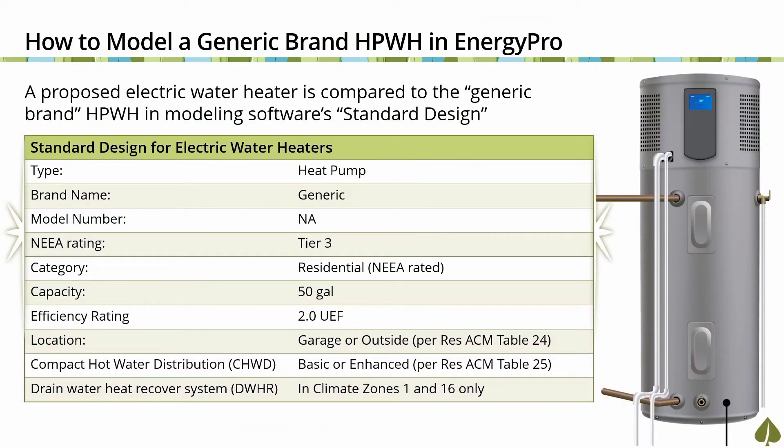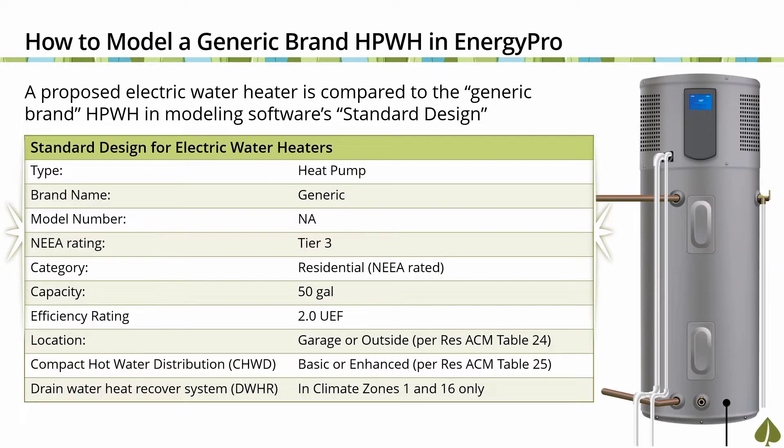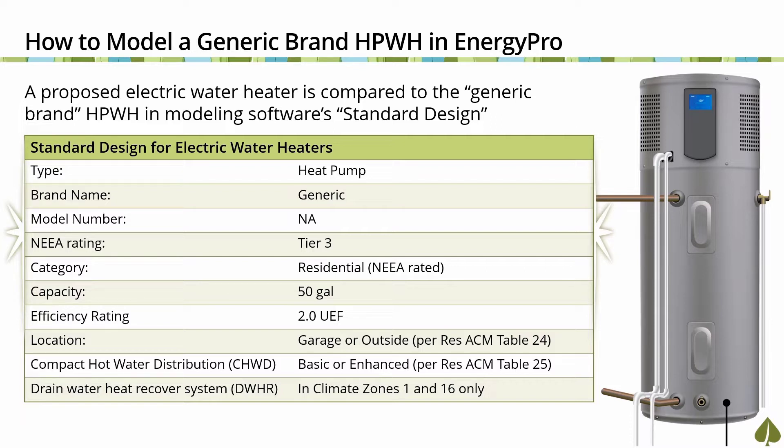When modeling low-rise residential buildings for compliance with the 2019 energy code, the standard design for domestic hot water systems serving individual dwellings is based on the prescriptive requirement found in section 150.1 C8 and the proposed water heater type being either gas or electric. When the proposed design specifies an electric water heater, the compliance software sets the standard design to a generic brand heat pump water heater, which includes the following specifications.